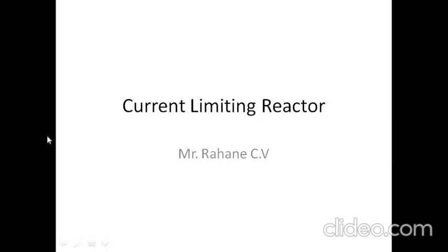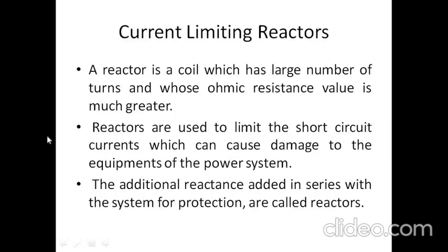We can start from the basics of reactor coils. A reactor is a coil which has a large number of turns and whose ohmic resistance value is much greater. Reactors are used to limit the short circuit currents which can cause damage to the equipment of the power system. Additional reactors are added in series with the system for protection purposes, which is called the reactor coil.